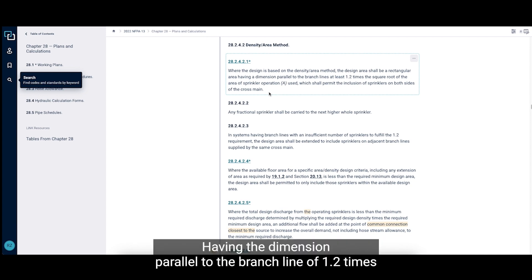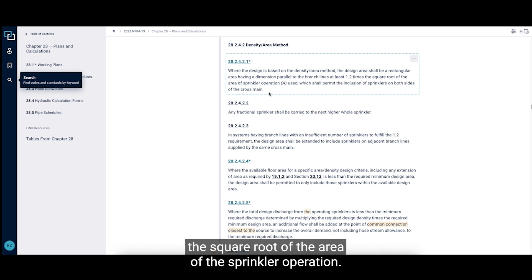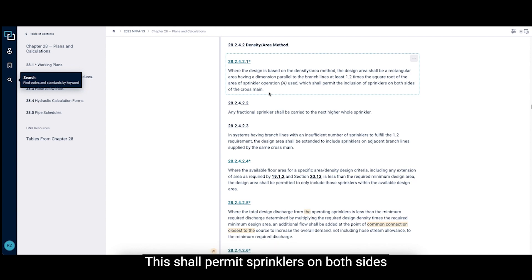Having the dimension parallel to the branch line of 1.2 times the square root of the area of the sprinkler operation. This shall permit sprinklers on both sides of a cross main.